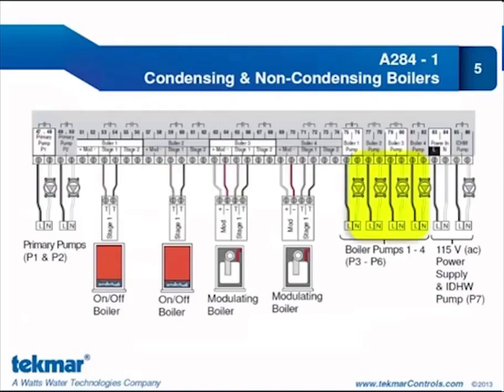Then we have our boiler pumps, with the same color distinction between pump terminals. In the 275, if you used an on-off boiler there was no way to also control that boiler pump. But now we have dedicated boiler terminals and dedicated boiler pump terminals, so it doesn't matter what type of boiler you're using — you can control it and its pump. On the right-hand side we have our 115V line voltage power in, and the terminals for the indirect domestic hot water pump. All of these pump terminals are dry contacts — we can switch up to 230V, 5A, one-third horsepower through these terminals.